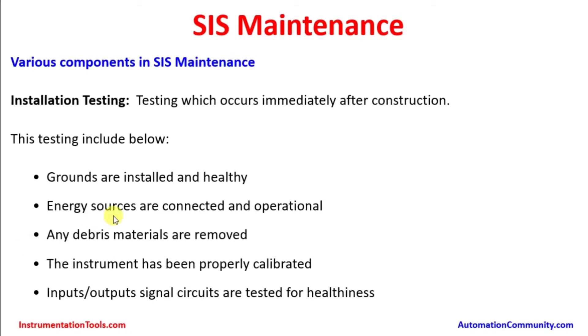The second requirement is that energy sources are connected and operational. During construction, multiple agencies are working — one contractor lays cables, another does terminations, another handles the switchgear side — so gaps can occur. These must be identified and cleared, ensuring all connections are done on both ends and continuity is checked. Also, any debris material must be removed from instrument tubing.